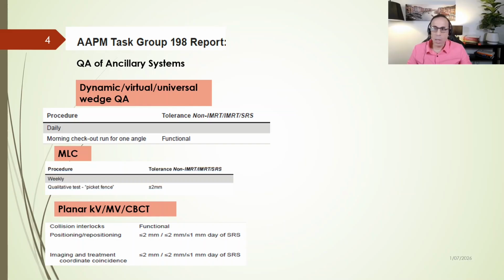And the other part is the imaging system. The imaging system is the eye of the linear accelerator. Daily QA includes checks of both kV and MV imaging to ensure they maintain accurate scaling and geometric constancy. The most critical assessment here is the imaging to treatment coordinate coincidence. In simple terms, we need to confirm that the center of the image used to localize the target corresponds exactly to the center of the treatment beam. Now we will look at these tests in more detail.